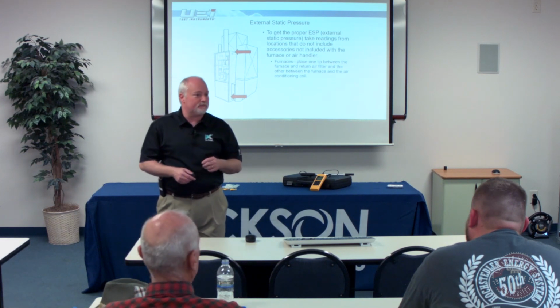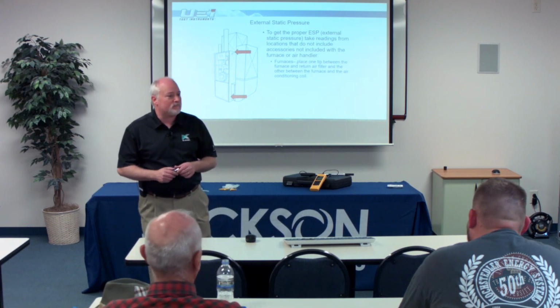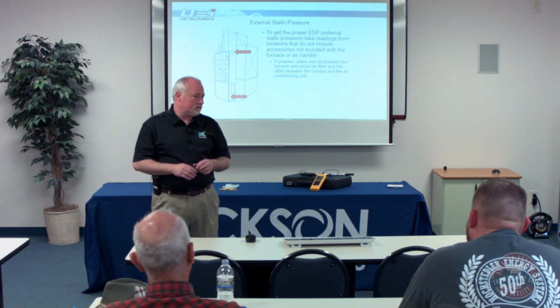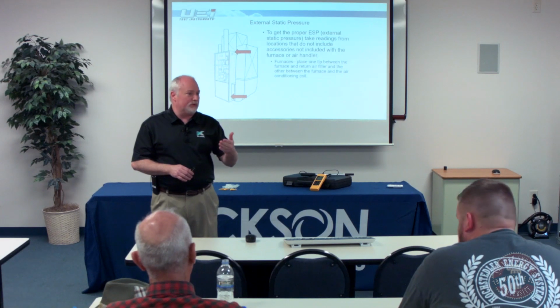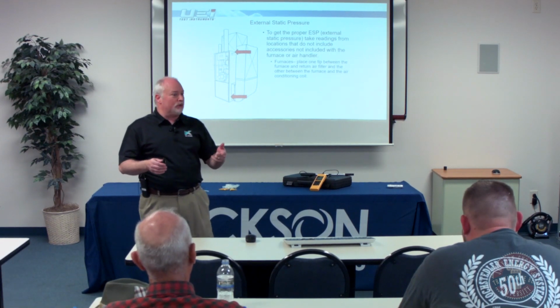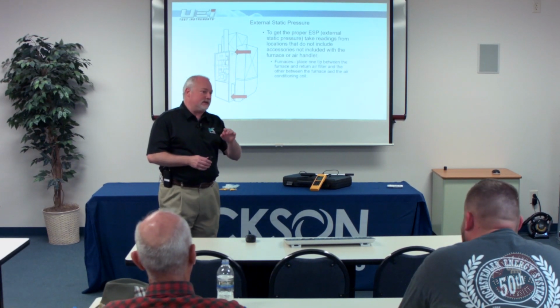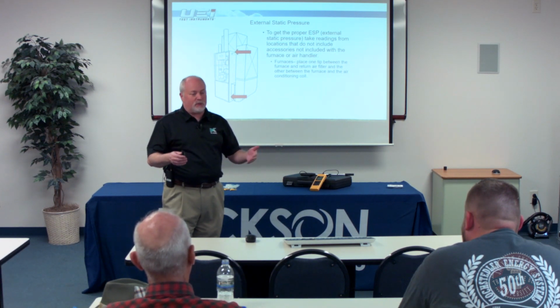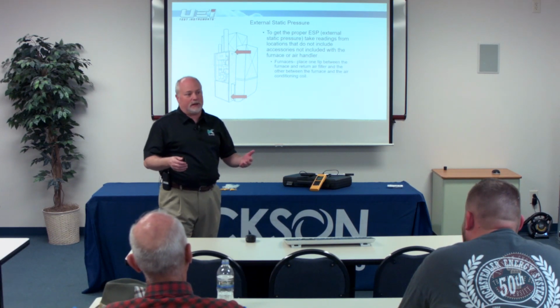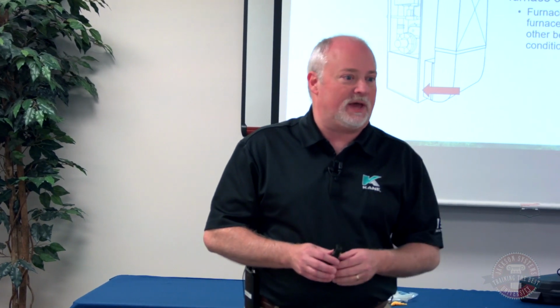Yes, we've got a question. Roger asks, can you use the EM201 for whole house pressure? For whole house pressure, it does go to pascals. That's one reason, if you've got one of our older EM201s, it did not read in pascals, which is a finer measurement and typically what they want for reading house pressure. If you want the 201B, as in Baker at the end, that reads in pascals.